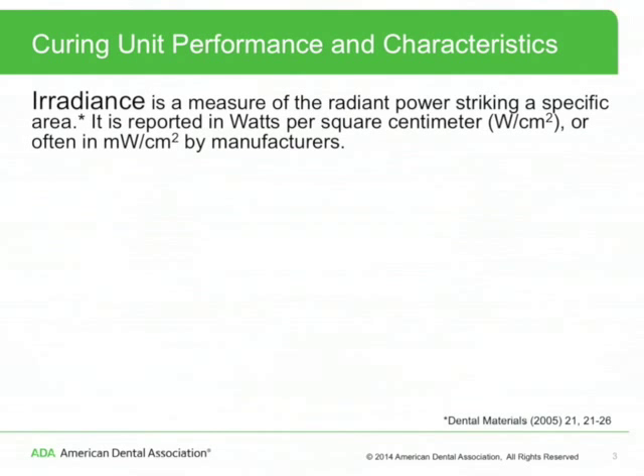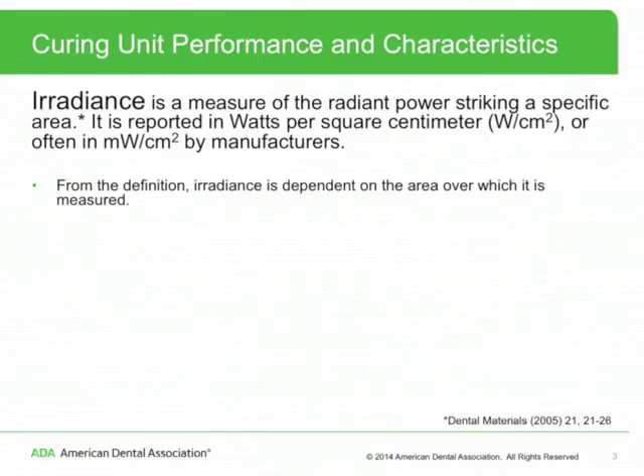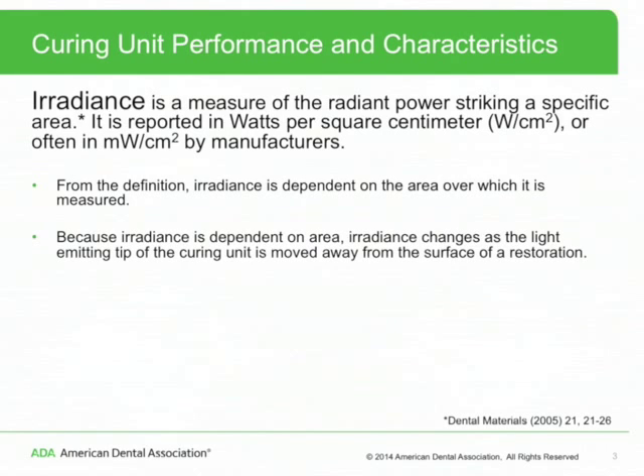Irradiance is a measure of the radiant power striking a specific area. It is reported in watts per square centimeter, or often in milliwatts per square centimeter by manufacturers. Irradiance is dependent on the area over which it is measured, and therefore changes as the light emitting tip of the curing unit is moved away from the surface of a restoration.